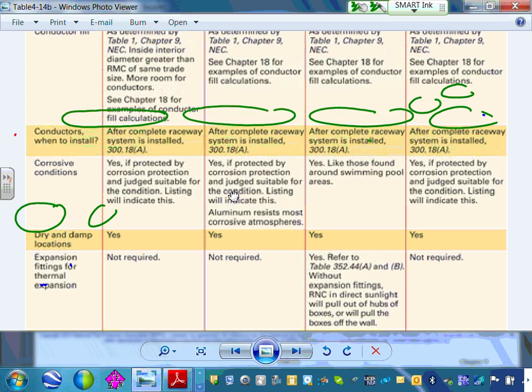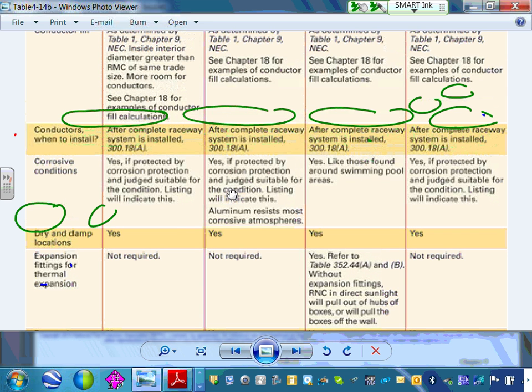Okay, so we got the conductor fill. Corrosion condition, if it's corroded, without getting into all these details, all of them guys can be installed with some type of protection. But if you have corrosion, any one of them can be treated to resist it. But we're designers and engineers. If you have any corrosion, your conduit of choice would be what? PVC. Even though the others can fit if treated, your conduit of choice is PVC.